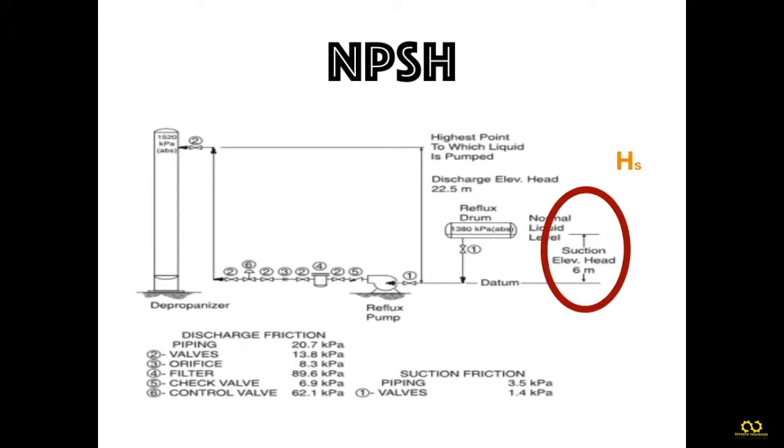Next is Hf, the friction loss. As I mentioned, cavitation appears during the suction stage, so you need to consider friction in the suction. The given friction for piping and valves on the suction side is: piping 3.5 kilopascals and valves 1.4 kilopascals. These kilopascal values should be converted to meters or feet. In this example I'm using meters.